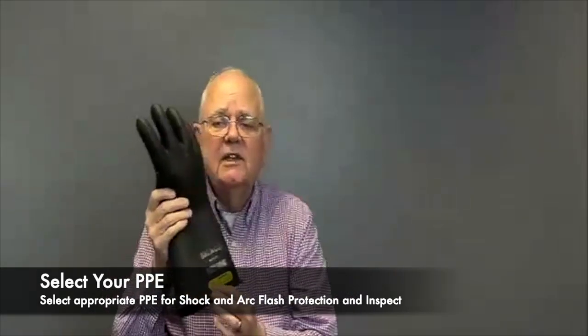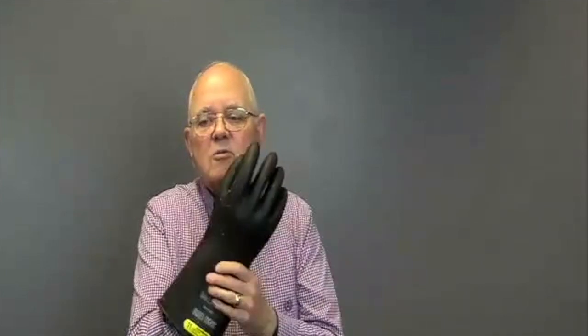Now, I don't have to memorize that because all that information is on the label. The label is also color-coded, but it tells me max use voltage, 17,000 volts AC. And like all rubber goods, they have to be inspected within the last 6 months. And you can look in your information on 70E about if the gloves have been sitting on the shelf for up to a year and so forth. But I have to test them every 6 months, send them out to be tested, and daily before use, I have to visually inspect my gloves. So none of that really changes. What has changed is the tool that I'm using. I'm going to a heavier type of glove, a thicker rubber.